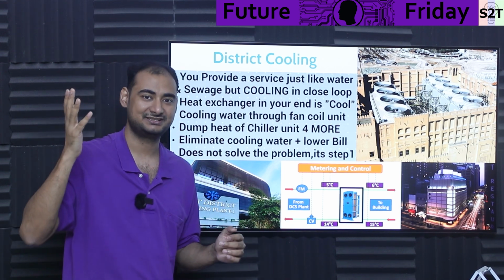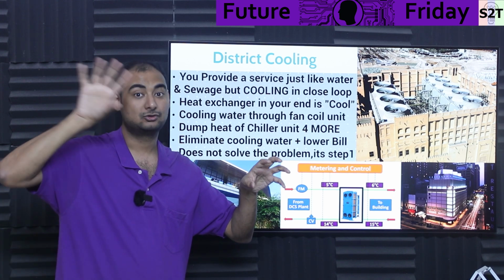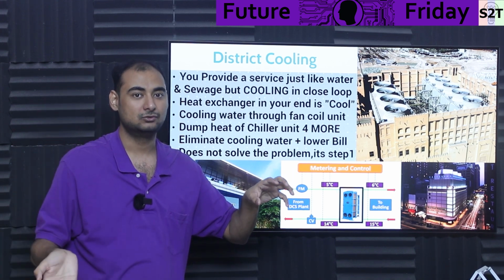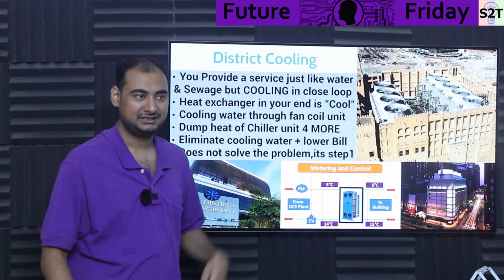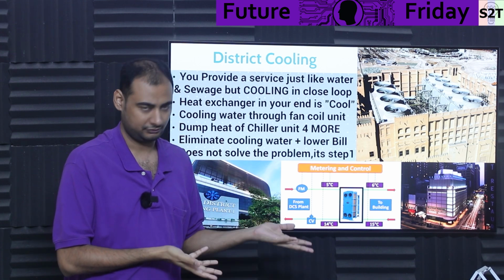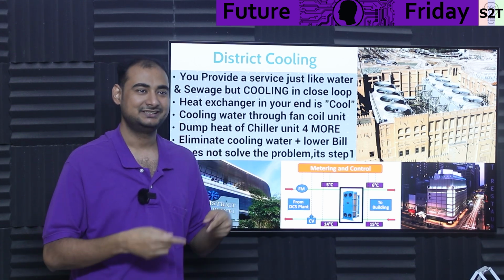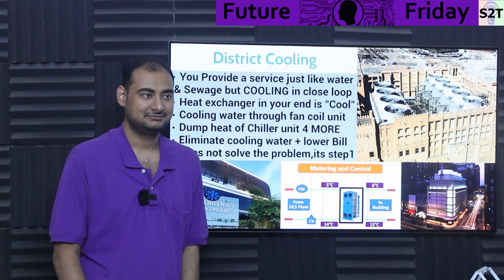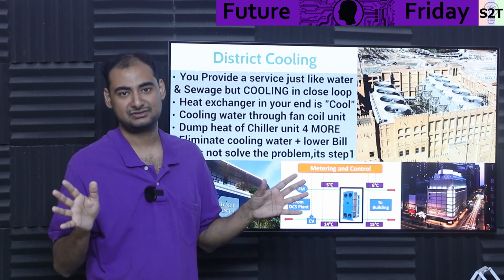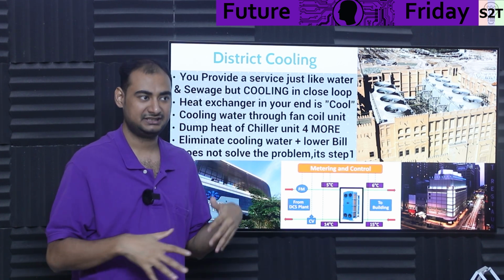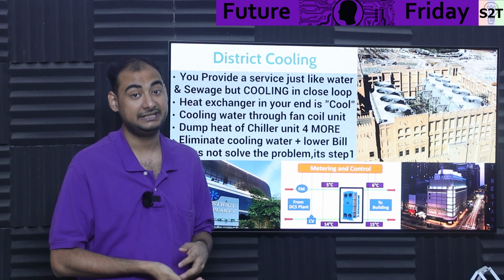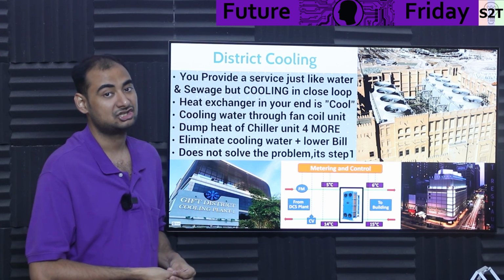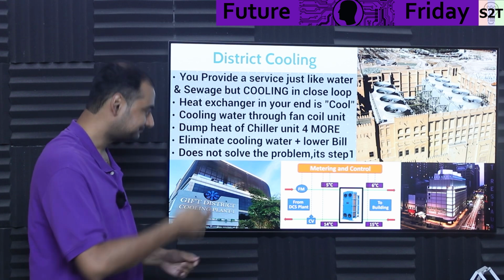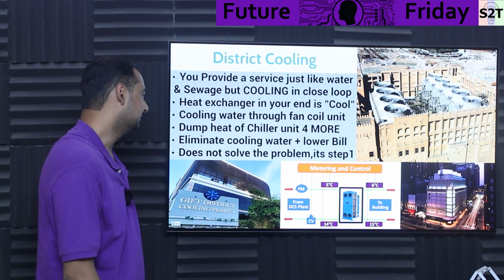But here's the deal: what happens if you want to cool something and the cold end, the condenser end, is already cool? Say you want to cool your room to 20 degrees Celsius and the liquid is already 15 degrees Celsius. Your COP on any refrigeration loop goes up exponentially. Instead of barely getting 4, you can easily get 8, and some chiller designs can touch 10. That's how we generally do this.